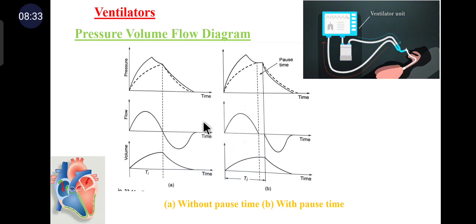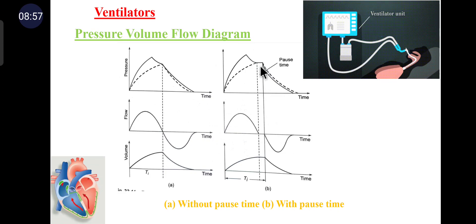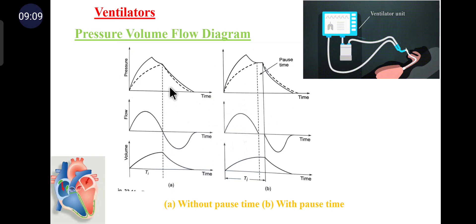The pressure-volume diagram is discussed here. It is necessary to provide a pause time between the cycling of the ventilator and the change from inspiratory flow to expiratory flow in the airway. During this pause time, the flow becomes zero when the alveolar pressure equals the airway pressure and a constant volume is maintained in the lungs. Ventilators producing a pause time during inspiration or expiration have certain advantages over ventilators without such a pause time, as shown in the pressure-flow diagrams with and without pause time.